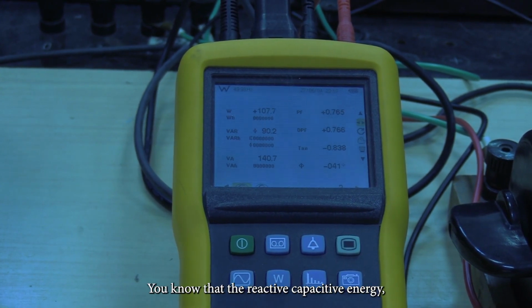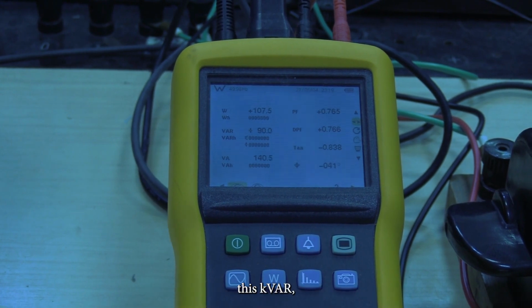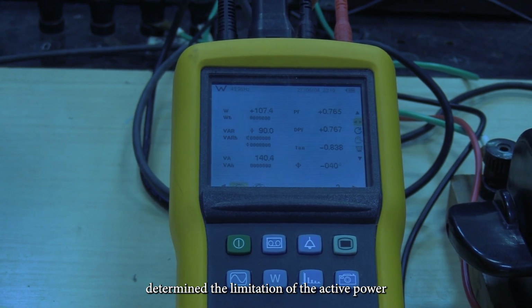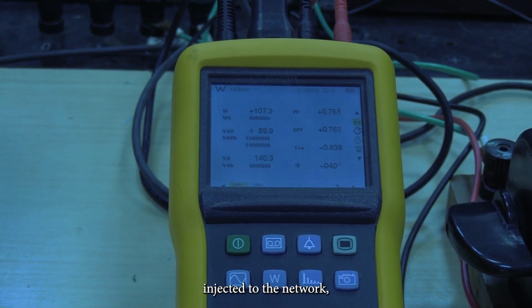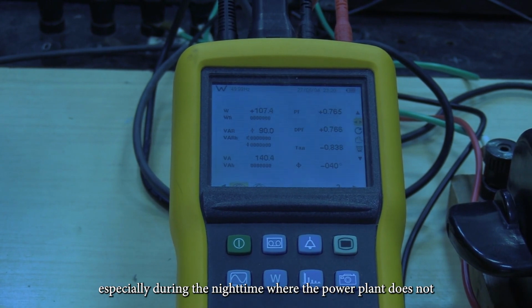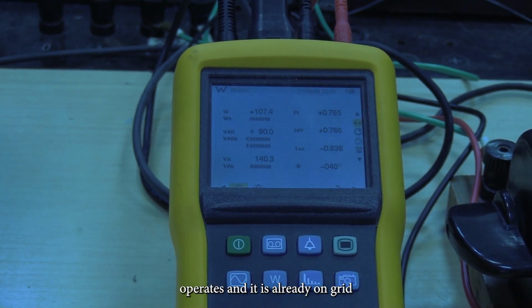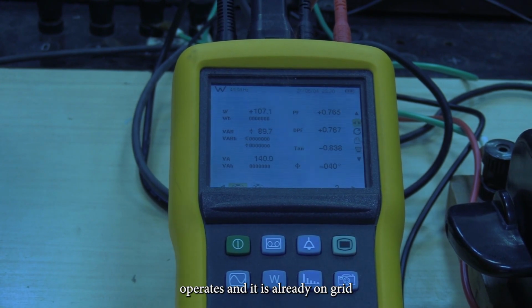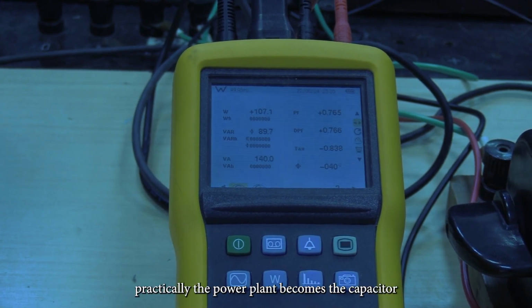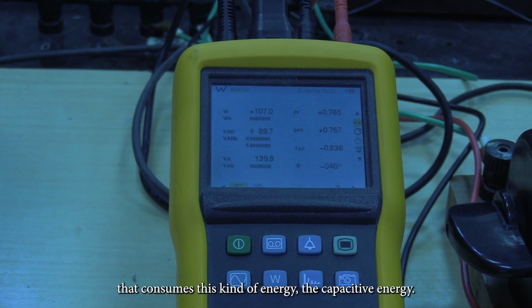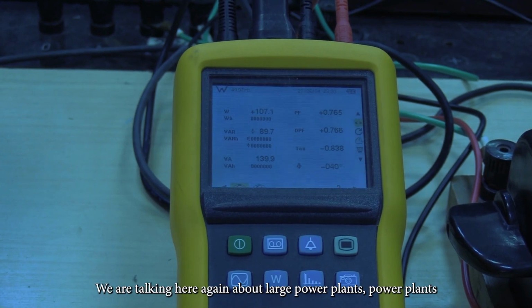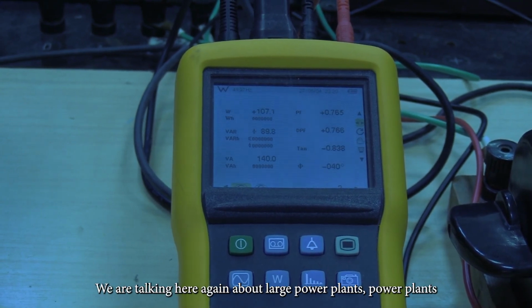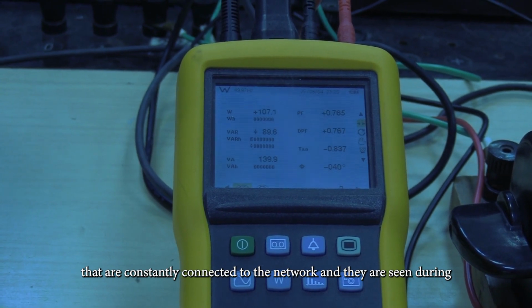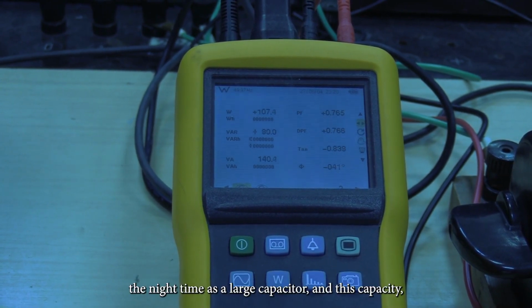You know that the reactive capacitive energy, this kilovar, determines a limitation of the active power injected into the network, especially during the night time where the power plant does not operate and it is already on grid. Practically, the power plant becomes a capacitor. A capacitor that consumes this kind of energy, a capacitive energy. We are talking here again about large power plants that are constantly connected to the network. And they are seen during the night time as a large capacitor.